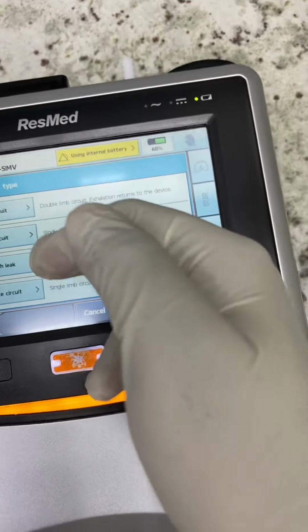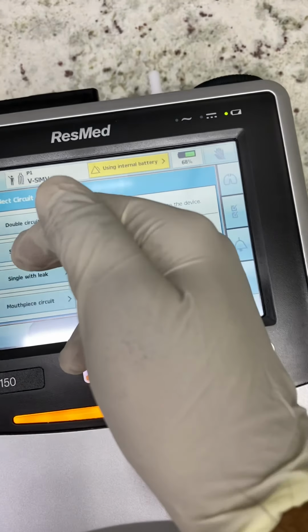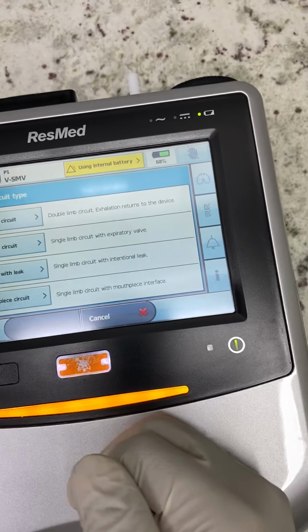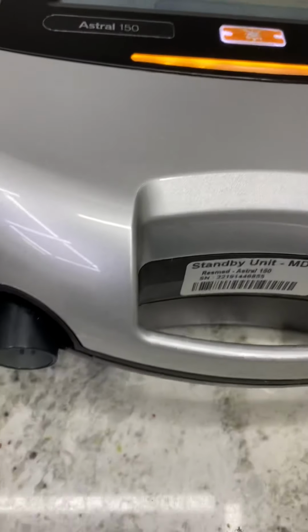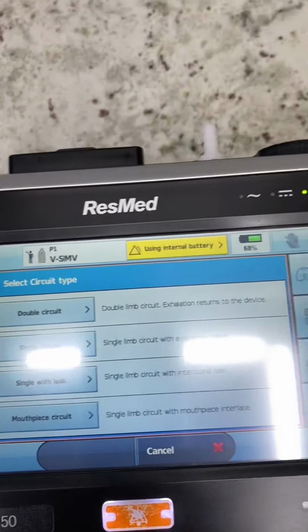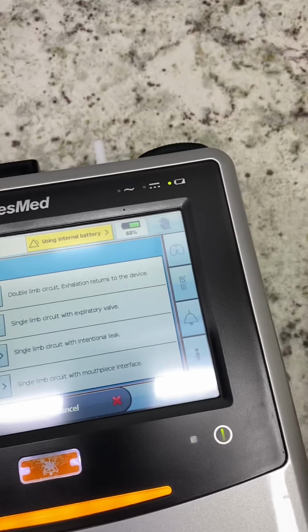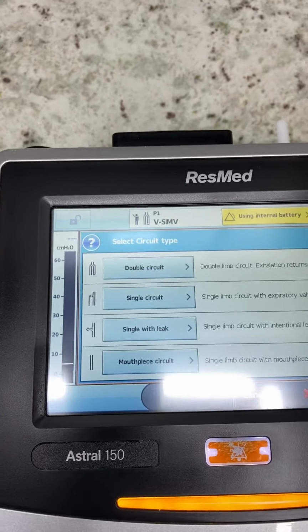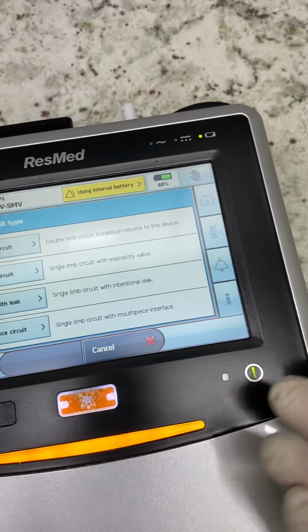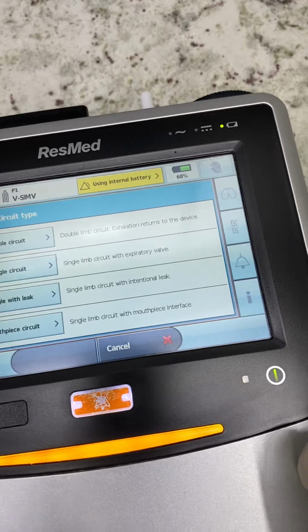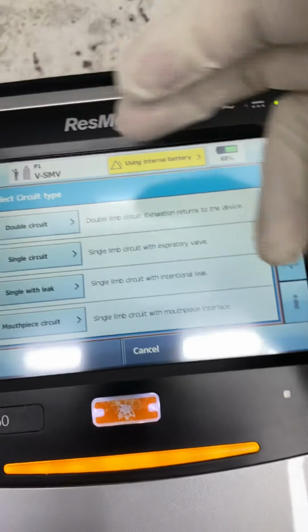You can use double circuit, single with a leak, or mouthpiece. So double, as I told you, the double limb in the exhalation. As I told you, this is the double limb. You can connect the inhalation and exhalation double tube. Or single circuit is like this one. You can use single with 2 valves, and single with a leak, just like a normal CPAP device. One single tube with exhalation mask or the leak port and mouthpiece. So since you are using the double circuit, you can use the double.